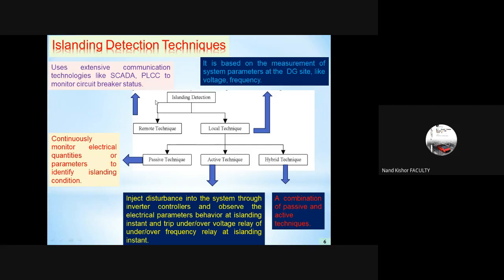Now, as I said, detection of islanding could be remote technique based or local technique based. In the case of a remote technique, we use the signal through the communication network, mainly from SCADA. That means we have the SCADA or the PLCC in the system, and we keep monitoring the signals at a definite sample rate from the SCADA and the PLCC, and thus monitor the status of the circuit breaker, whether the circuit breaker is on or off. Based on the status of the circuit breaker, we come to know whether the DG is islanded or not. So that is one way. But this is communication based here.